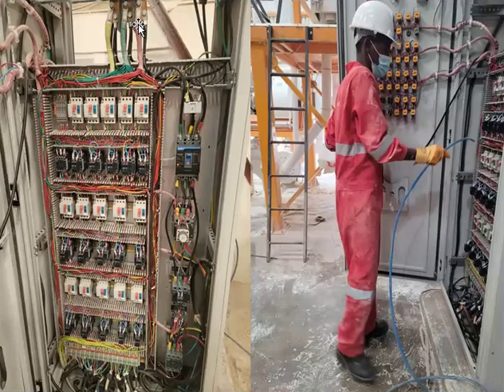Then there is also dust. Dust can affect this. So also you find a situation where the cable has been used for a long time and it is reducing in resistance, and therefore the cables get burnt.